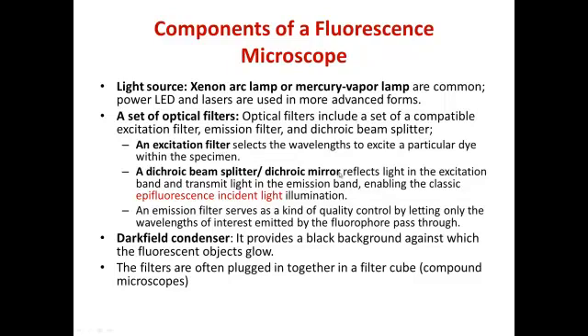There is a dichroic mirror that can reflect the light in the excitation band and transmit the light in the emission band, enabling classic epifluorescence incident light illumination. An emission filter serves as a kind of quality control by letting only those wavelengths of interest that are emitted by the fluorophore pass through.